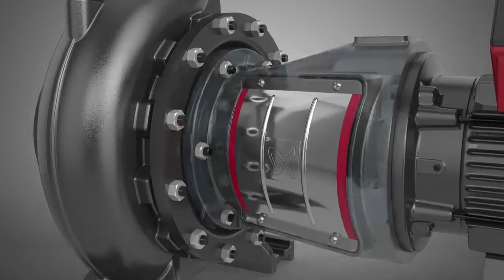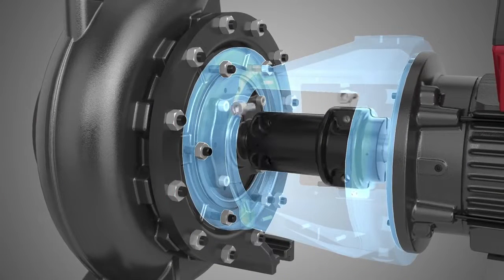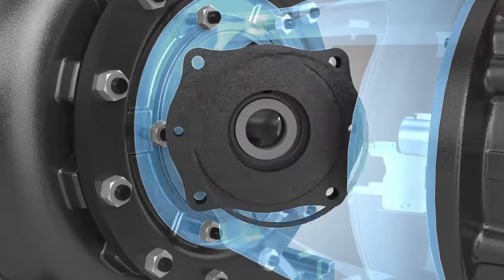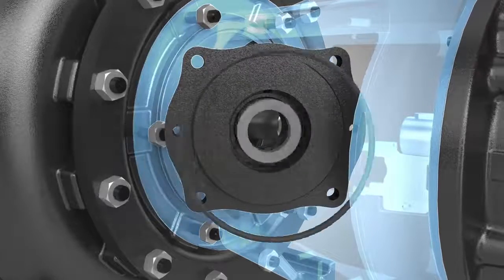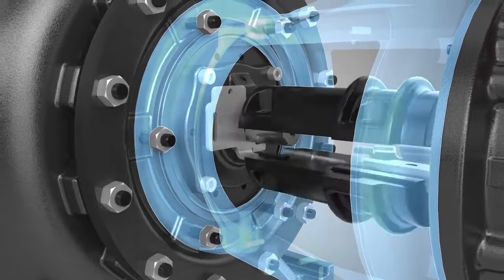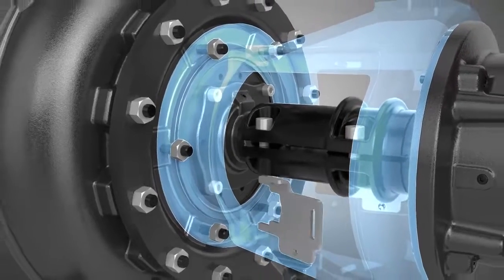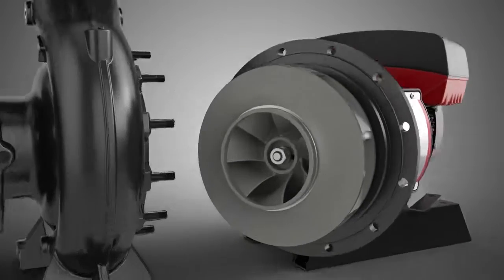The NBS has been designed to protect the life of the rotating assembly. But when it comes time for routine maintenance, we've added features to make it as easy and fast as possible. The split-coupled design allows for easy seal replacement without removing the motor. And with a back pull-out design, there is no need to disturb the piping.